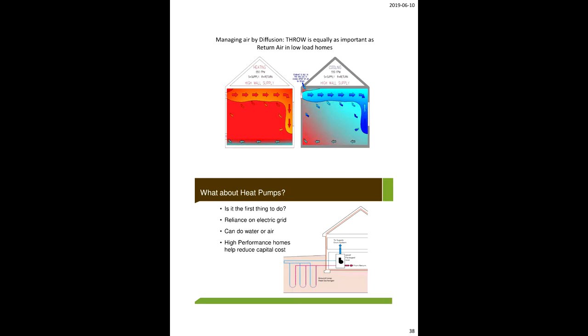Let's get rid of some ductwork. Let's put high wall registers in, let's move the air a little faster, not high velocity, mid velocity. Let's get it out of the occupied zone, 6 inches from the ceiling, and let's start to mix the air quietly but effectively, mixing the air in the room.